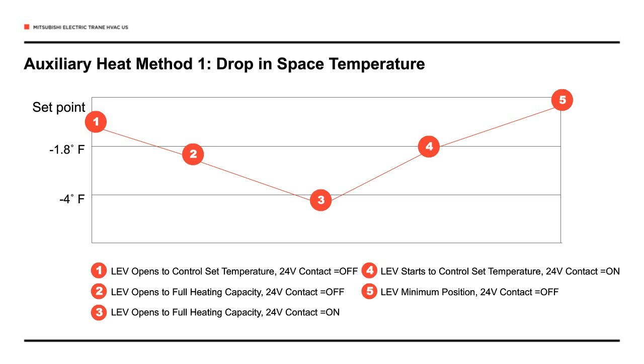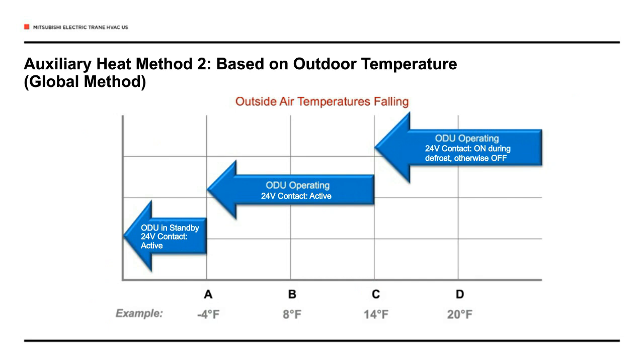We also have a method we call the global method, where instead of doing each space standalone, we're doing the whole system as one system. So we're switching the entire VRF system over to auxiliary heat. A good example of this is, as I mentioned earlier, a school. Maybe a school has boilers and hot water unit ventilators, and they're adding a VRF system for cooling. Maybe it makes sense at, say, 15 degrees to just switch the whole system over to the backup boiler system, fired by a natural gas-driven boiler.